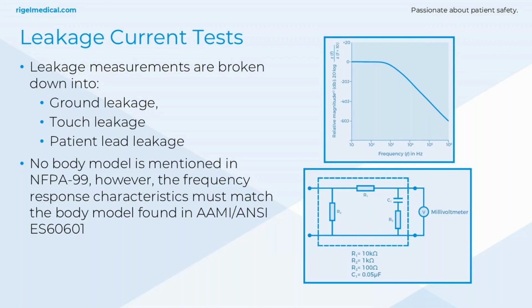Of course, you could make up your own version of this in a workshop with some type of voltmeter and basic components, but you'd also need something to simulate the fault conditions, such as open ground for touch leakage. So using a dedicated safety analyzer is what most workshops are going to do, with a very simple safety tester. And those in our SafeTest range, like the 60 plus, ensure you're getting the right measurements.